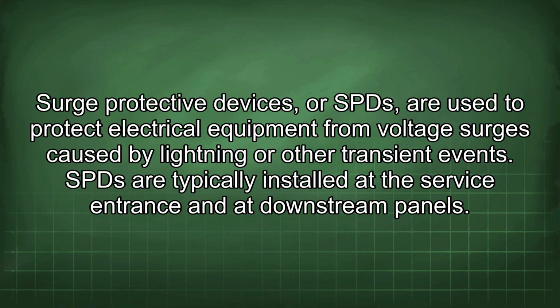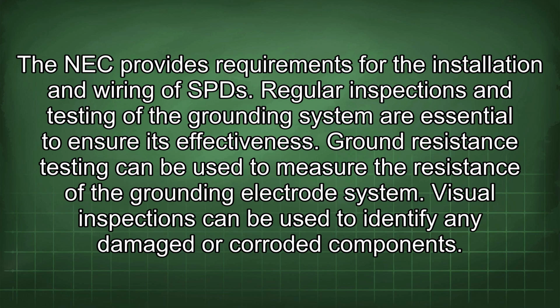Surge protective devices, or SPDs, are used to protect electrical equipment from voltage surges caused by lightning or other transient events. SPDs are typically installed at the service entrance and at downstream panels. The NEC provides requirements for the installation and wiring of SPDs.